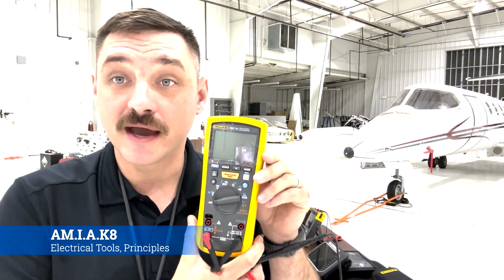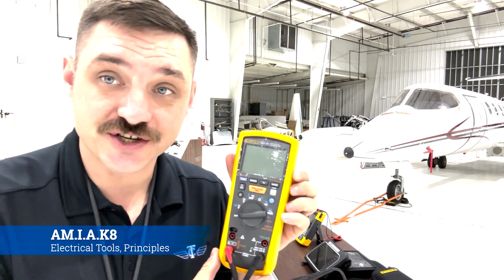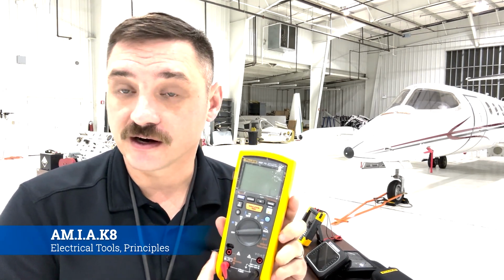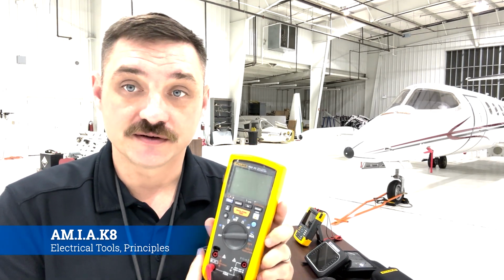Okay, this is a megaohmmeter, right? It is a Fluke 1587, and it's primarily used for doing insulation testing. The most common usage for this is trying to figure out the health of electric motors, hooking up to one phase to ground and seeing what its insulation is, and then going through other phases and making sure that all of the phases read about the same.